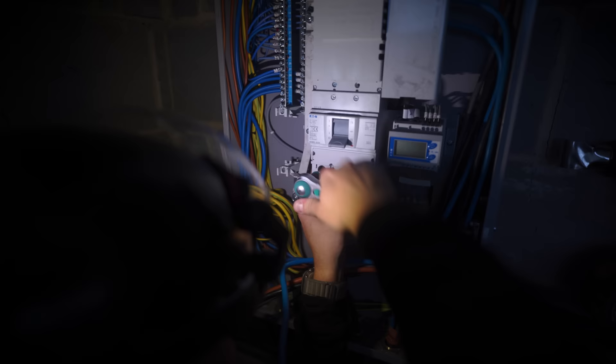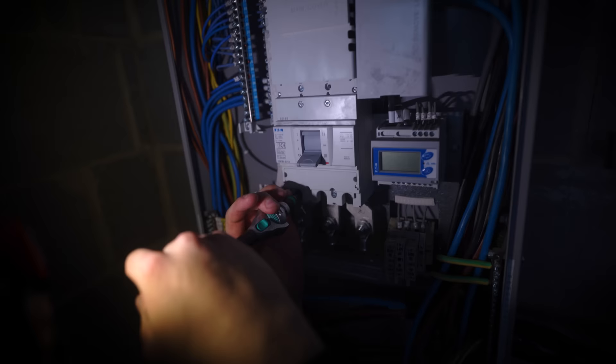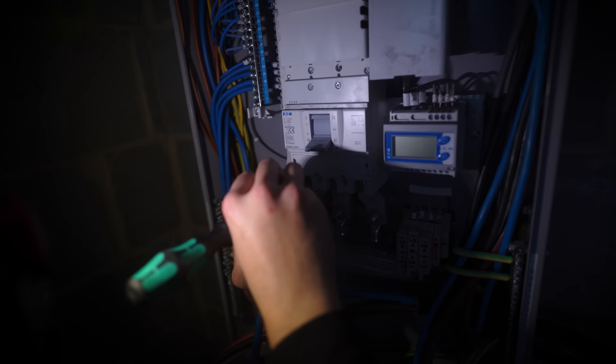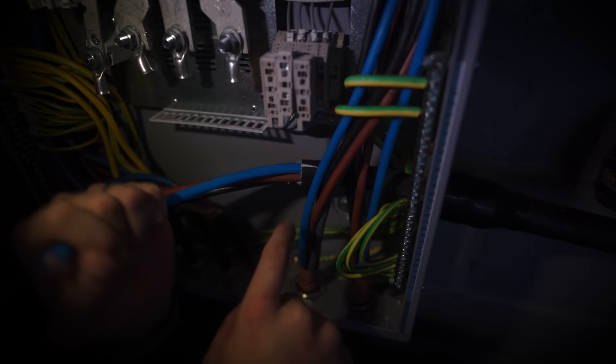See, this is the problem. I'm actually going to have to whip that all the way out, I think. The channel nut in the back is spinning. I'm going to have to call Steve and see what he wants to do. Where I pulled this back just a little bit, it's split — the LSF sheath just split. So yeah, you just want to be careful with that.